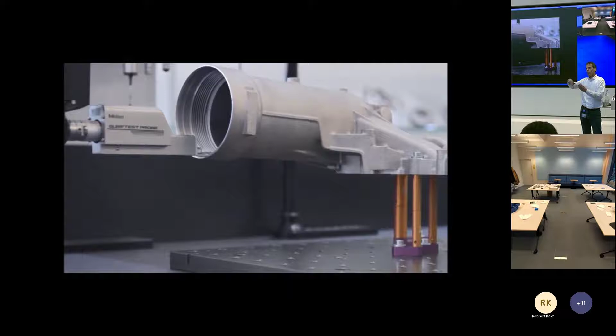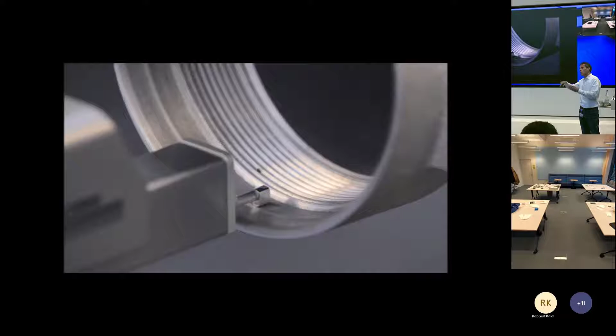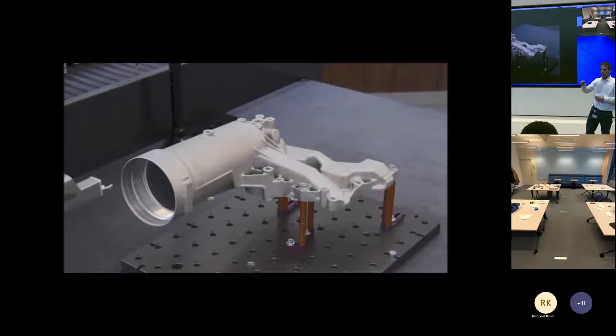So if you also want to do contour, you go from the CMM to a contour measuring instrument, because there your radius is 25 microns. If you want to go deeper in roughness, your radius will become 2 microns. So in this case, the standard radius for roughness measurement is 2 microns. The CMM is only used to do the positioning of the roughness tester.